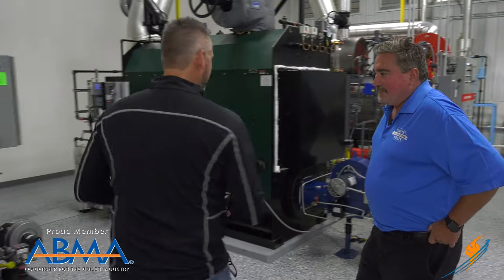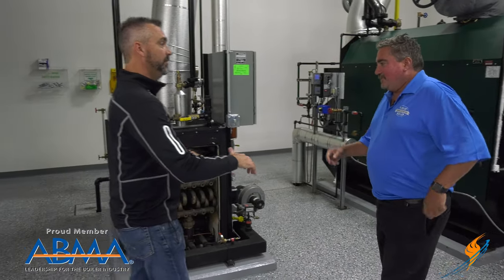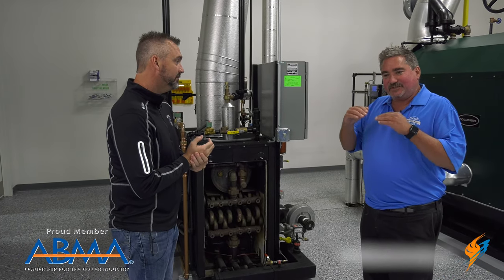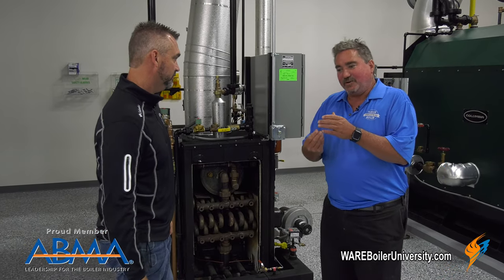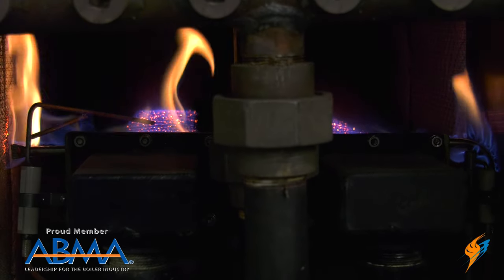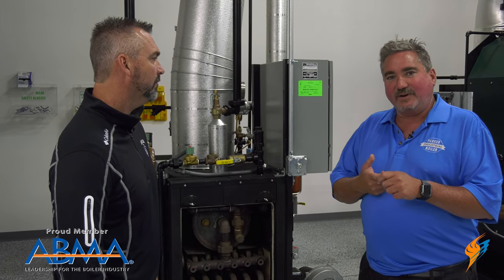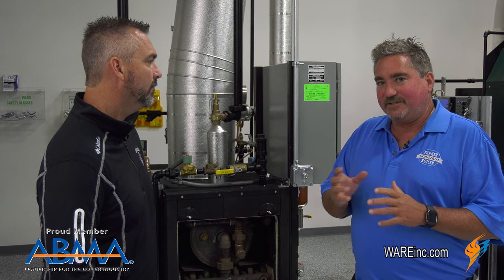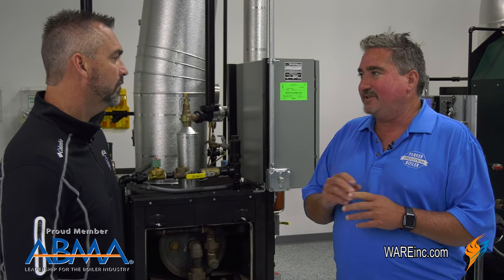Let's talk a little bit about the boiler. It's an atmospheric boiler. Our actual atmospheric boiler is just a simple barbecue burner — it's got a little orifice on the bottom with a venturi with nine slots in it. There's no fan assist; it's just the velocity of the gas going that mixes the air and it goes. The nice thing is you don't have a fan with a parasitic energy loss, you don't have air-fuel ratio mechanical linkages that get out of whack, and you've got a much more even, uniform heating surface.